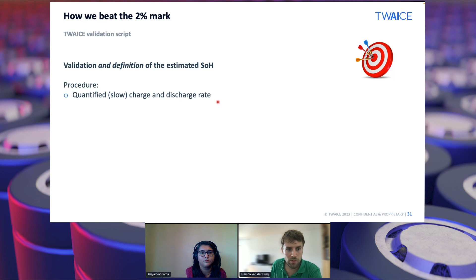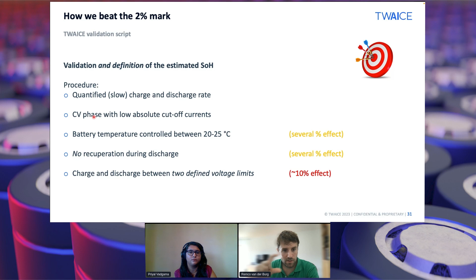The constant voltage phase has to have a very low absolute cutoff current that is specified. The battery temperature needs to be controlled. There's no recuperation allowed during discharge, and the two voltage limits have to be specified precisely. This is exactly the definition that we follow in the SOH that we provide.